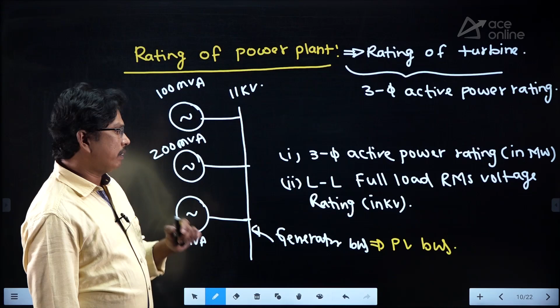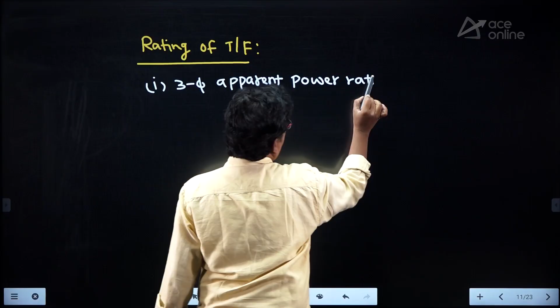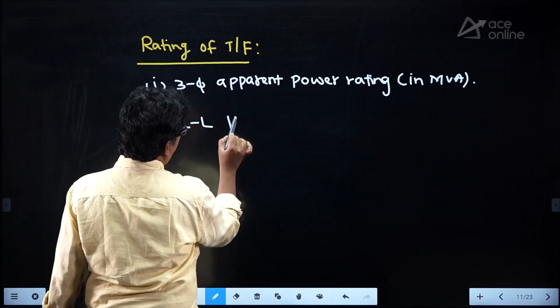Next one is rating of the transformer, which is a shunt device. Right? So here first one is 3-phase apparent power rating, which should be given in MVA, and second one is voltage rating. For a transformer we have to give two ratings, primary voltage rating and secondary voltage rating. So primary no load voltage rating, secondary no load voltage rating. Line to line, primary no load, it's not full load, it's no load. Voltage rating in kilovolts.